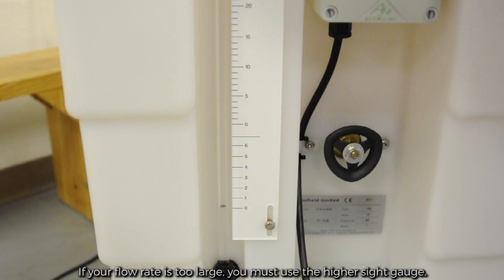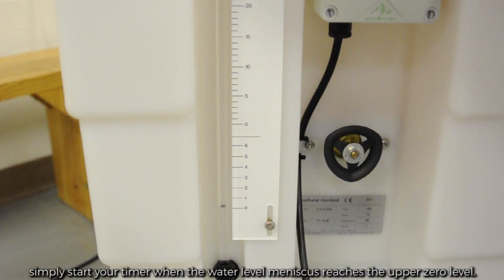If your flow rate is too large, you must use the higher sight gauge. In order to accomplish this, simply start your timer when the water level meniscus reaches the upper zero level.